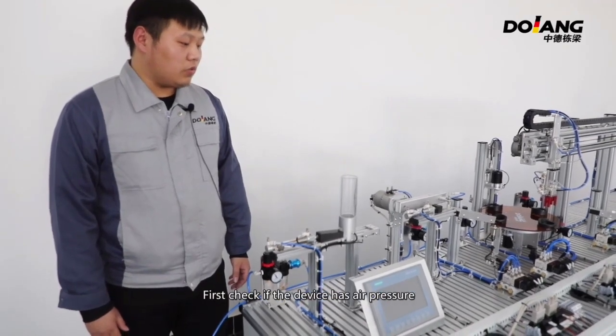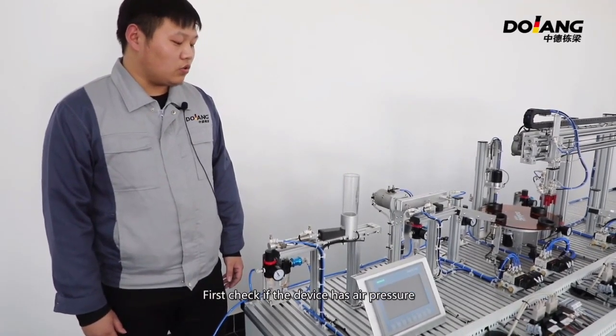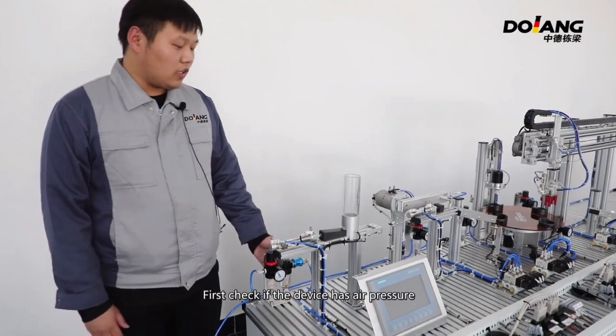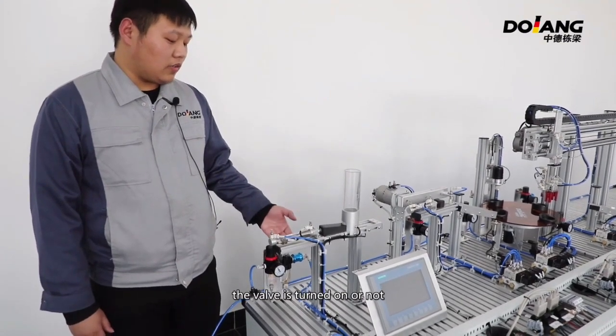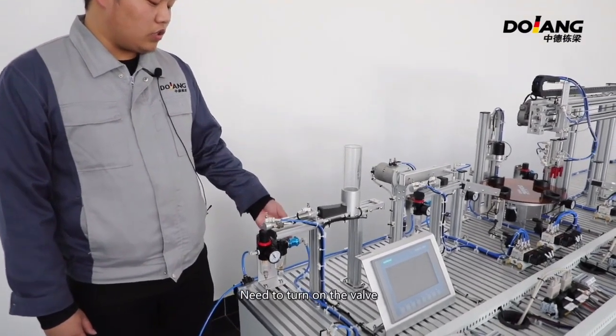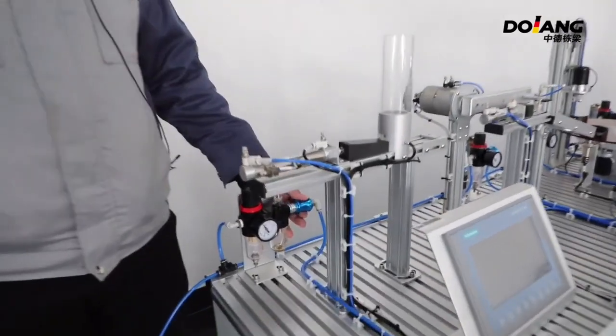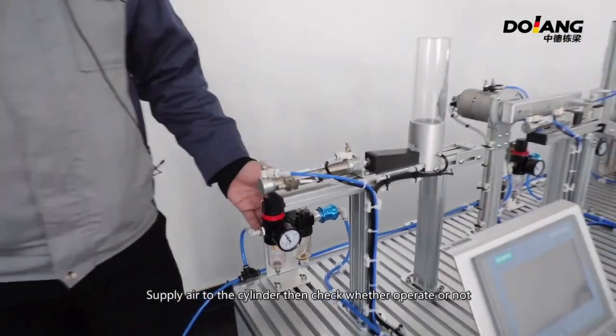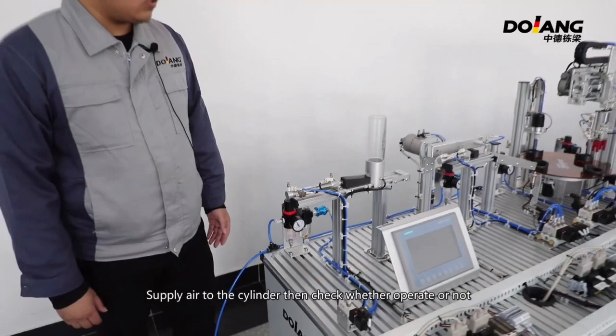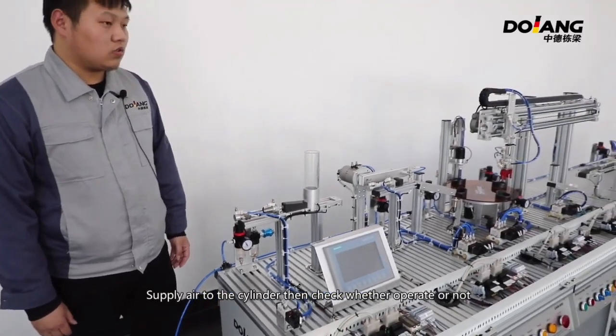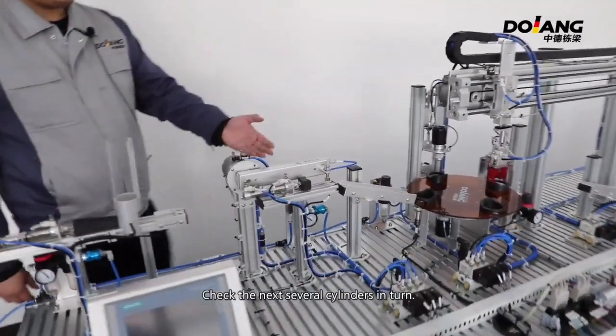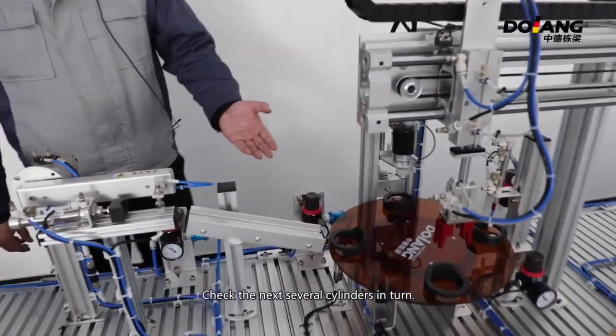Second, when the device doesn't operate, first check if the device has air pressure. Check whether the valve is turned on or not. It needs to be turned on. Supply air to the cylinder, then check whether it operates or not. Check the next several cylinders in turn.